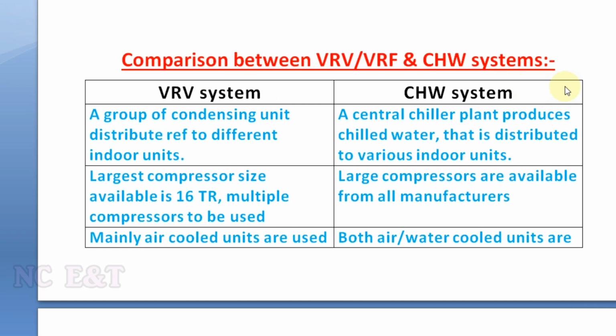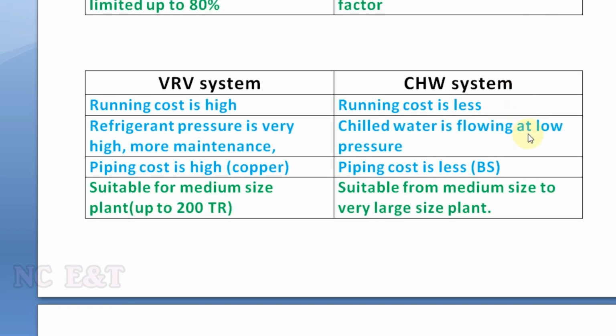Number 2, the largest compressor size available is 16 ton, so multiple compressors need to be used in the VRF system, whereas for chillers large compressors are available from all manufacturers. Number 3, mainly air cooled units are used, whereas in chillers both air and water cooled units are used. The running cost for the VRF system is high, and the running cost for the chilled water system is less. In the VRF system, refrigerant pressure is very high, so more maintenance and more chances of leakage, whereas chilled water is flowing at low pressure, so less chance of leakage.